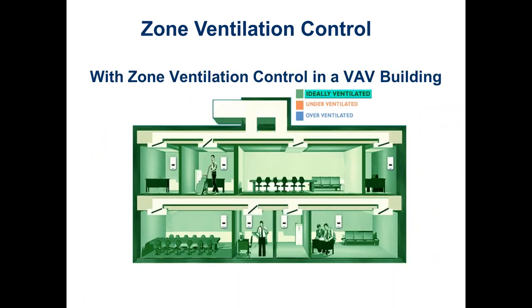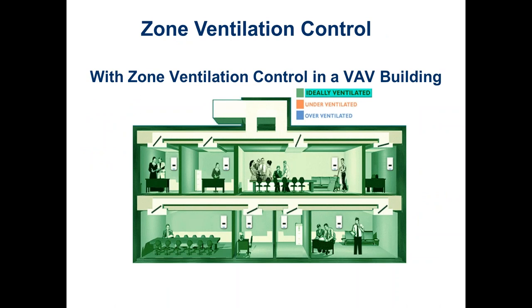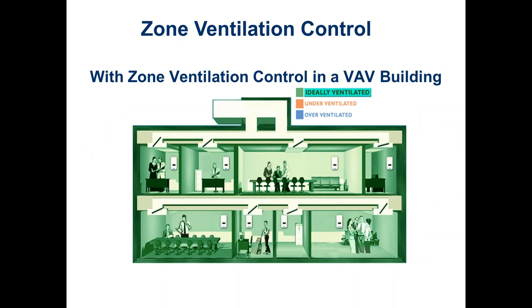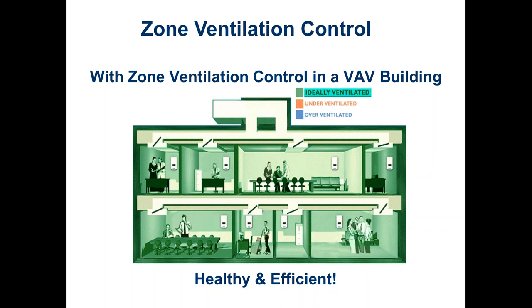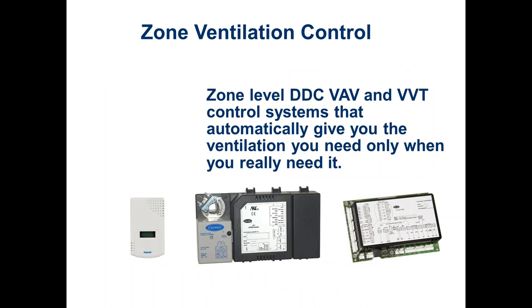If we actually start measuring ventilation rates based on CO2 in individual spaces, we can modulate VAV dampers to ensure each space gets the right amount of air. On a constant volume system it's simpler — just one outside air intake damper to modulate. For a VAV system you must have DDC controls; the CO2 sensor per VAV box reports to that box controller and modulates the damper based on occupancy. The air handler controller then looks at all VAV controllers — if any cannot achieve the desired CO2 set point by modulating their zone damper alone, the main air handler opens the outside air intake more.